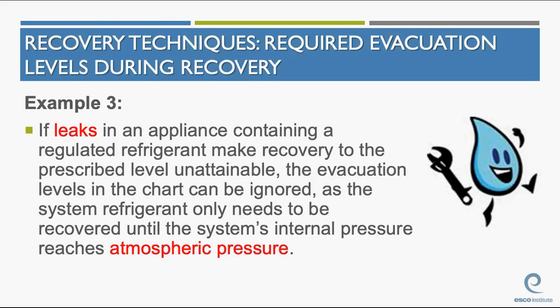If leaks in an appliance containing a regulated refrigerant make recovery to the prescribed level unattainable, the vacuum levels in the chart can be ignored as system refrigerant only needs to be recovered until the system's internal pressure reaches atmospheric pressure. In other words, if you have a leak, okay, and you cannot pull a vacuum on a system with over 200 pounds of refrigerant in it, all you can do is get it to atmospheric pressure. It's the best you can do, and the EPA acknowledges that. You can't pull a vacuum on things that leak. Okay, easiest way to know if something leaks. You can't pull a vacuum.